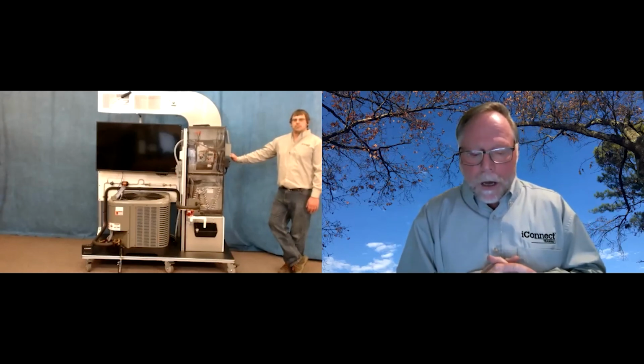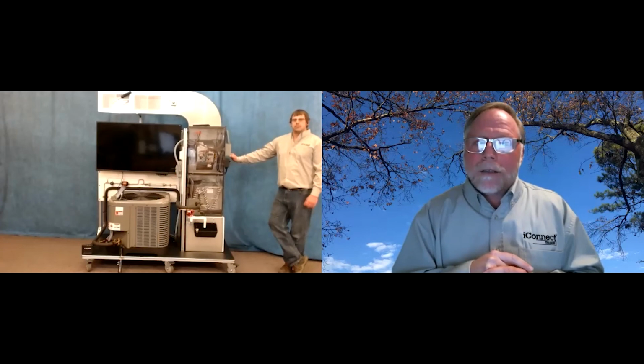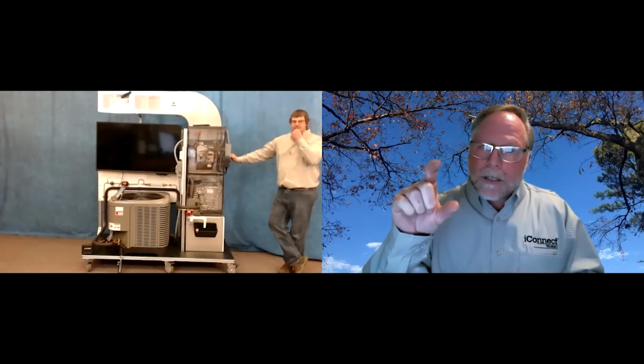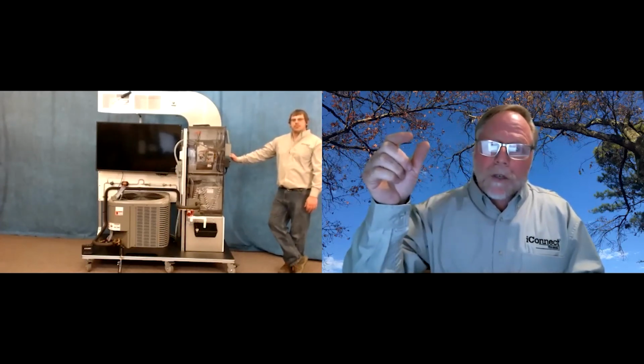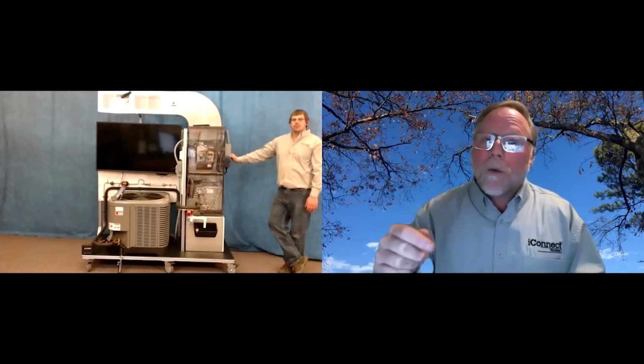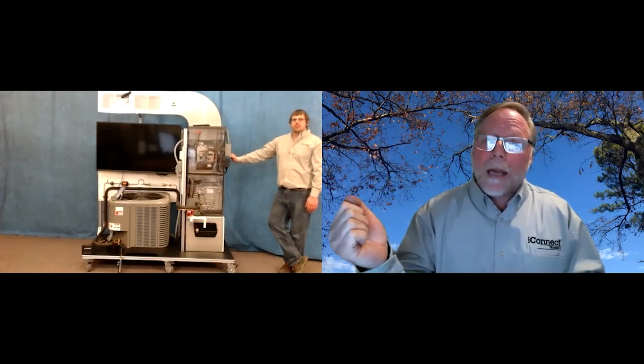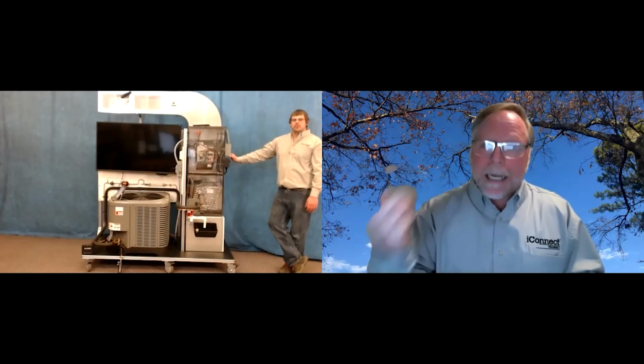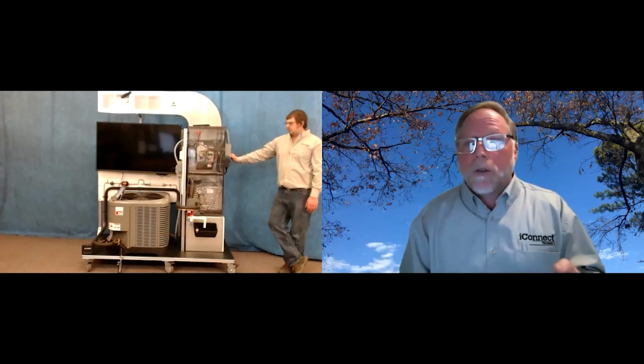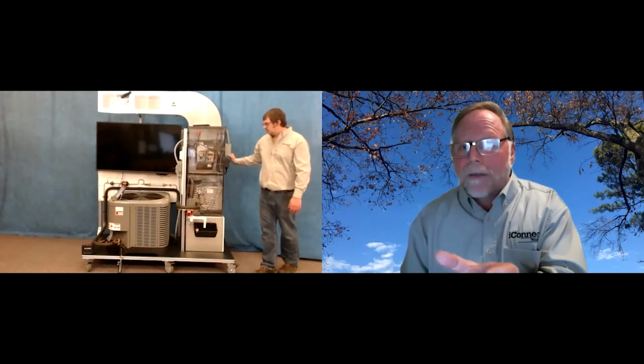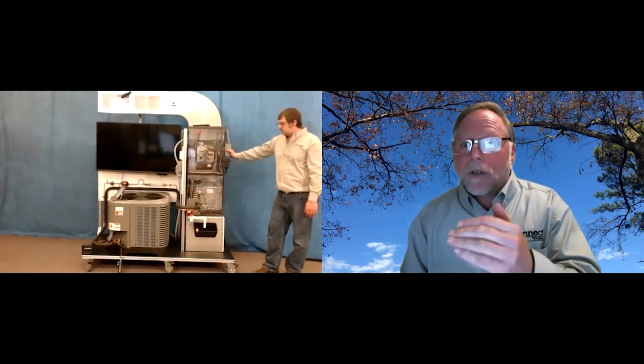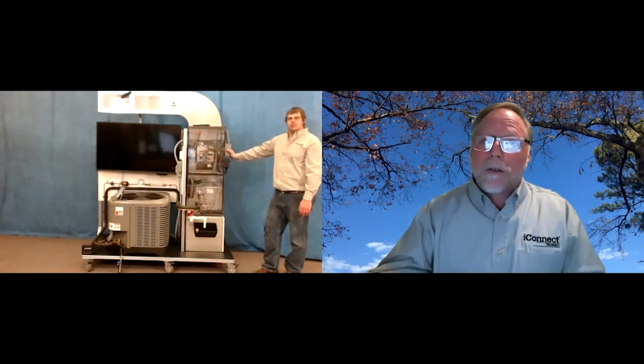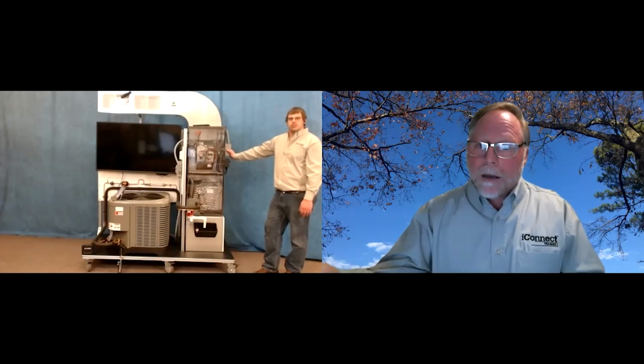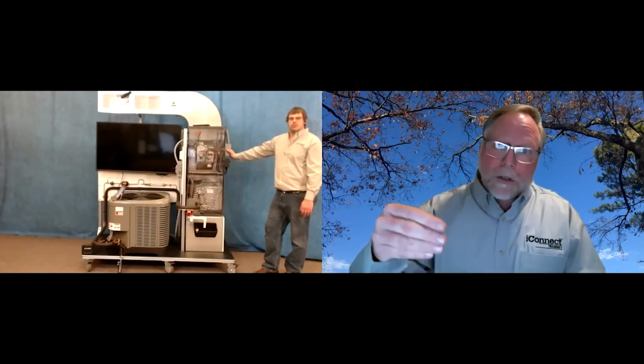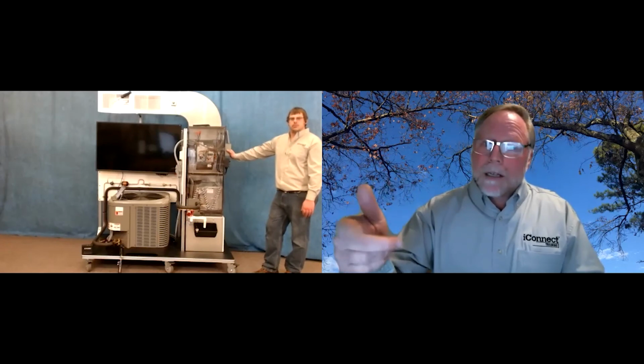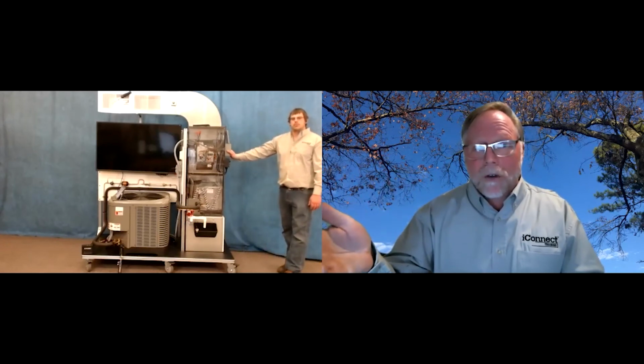Lesson number 4 is the operation of the EZ Trap. You can pull out the safety switch, show it how it works. You can fill it up with water and then block the drain and watch it actually open up and take the unit off. You can also then let the auxiliary drain pan fill up. And when it gets to a level, watch it take out the unit as well on safety. And then you can have the students wire it up and then test it and see if they did it right, see if it actually takes the unit out.